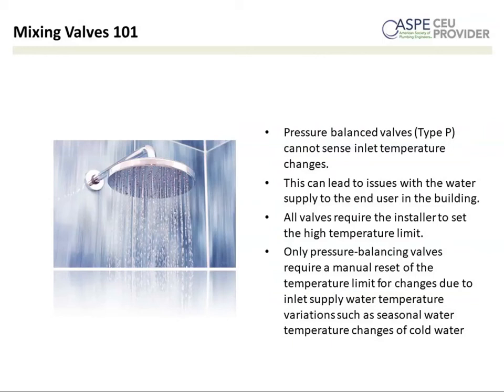And again, it's critical with any type of valve to make sure that the limit stops are installed. And with pressure balancing valves in particular, because they can't sense temperature, it's very important to make sure that the limit stops are readjusted going from season to season. So, for example, if a valve is installed in the winter and the cold water is 40 degrees, and then by the time summer hits, maybe your cold water has risen to 60, 65 degrees, that's a 25-degree increase. Now, that full 25 degrees is not going to be translated to your outlet temperature, but it is going to increase the outlet temperature based on the same handle position. So again, it's an important thing for the maintenance crew to be going room to room and making sure limit stops are readjusted.